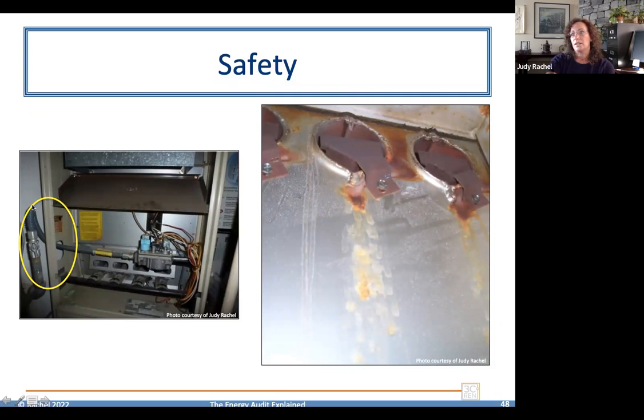On the left here, just to let you know, this is flex gas line going through the furnace assembly, and that's not legal, mostly for seismic safety. In an earthquake in particular, this line can be very easily severed, so it needs to be hard pipe going through there. This is very typical on older homes. There's been combustion gases condensing outside of the burners in this furnace, so there's something going on. There's some kind of negative pressure problem going on with the furnace.